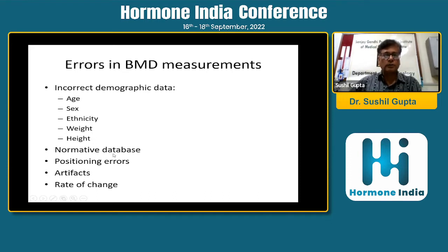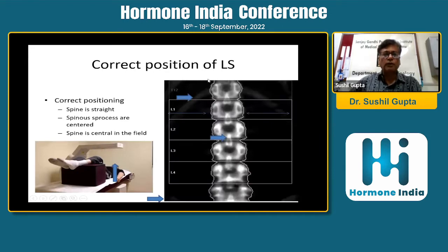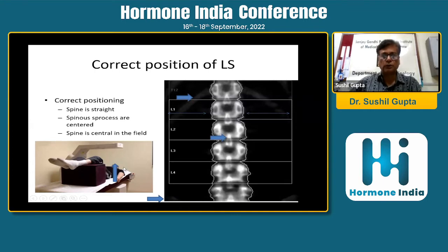One has to look at the normative database, which is specific to the machine. There could be positioning errors of the spine and hip, since these are the two sites we commonly measure, and there could be problems with artifacts. When looking at lumbar spine positioning, the spine should be straight, the spinous process centered in the region of interest. The person lies on the table with legs placed on a block perpendicular to the table, which brings the spine into the center of the field.